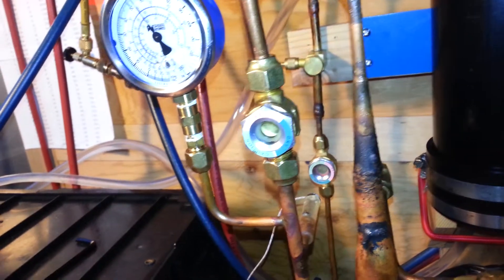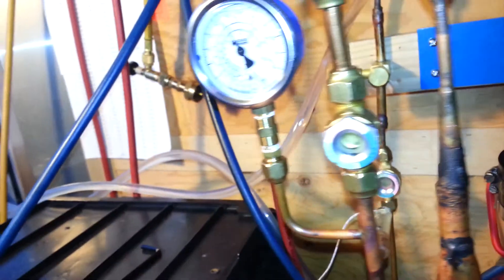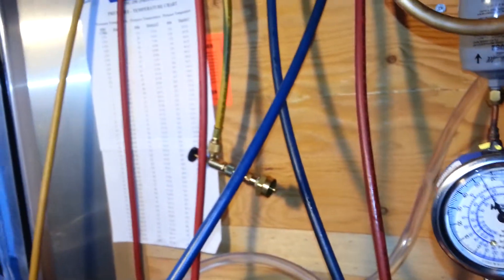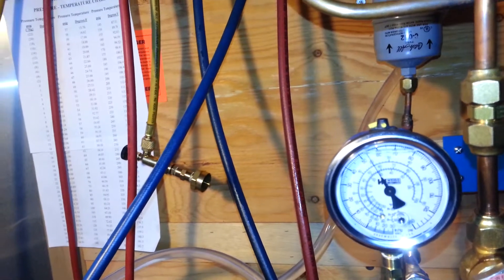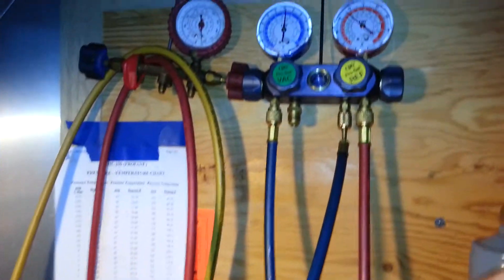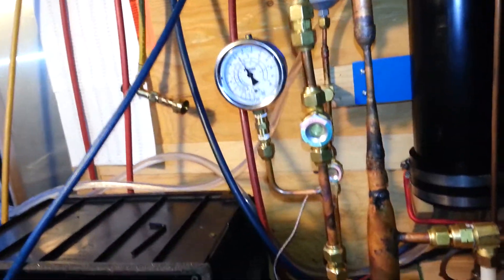Just fooling around a little bit here tonight, the ejector — I get the largest pressure differential I've seen as high as 10 PSI. 10 PSI is pretty difficult to achieve, but usually it's around 6 to 8. 8 is very common. Getting anywhere above that is quite difficult.